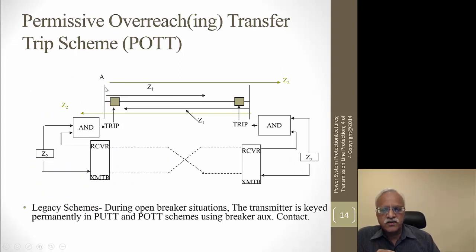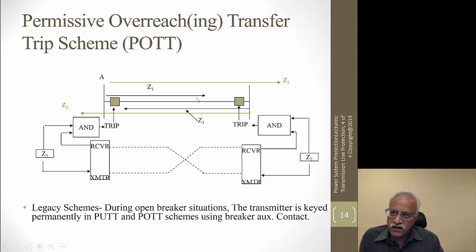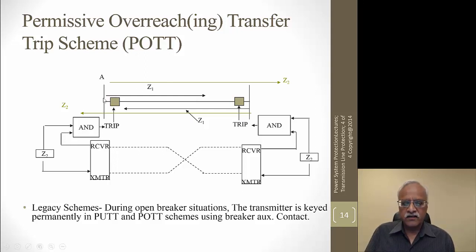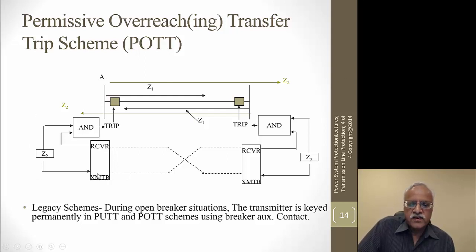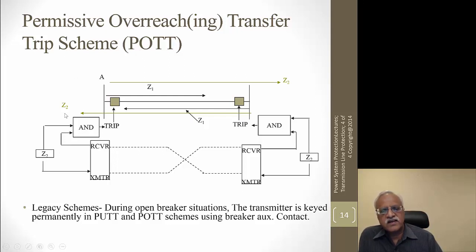Another scheme uses an overreaching zone instead of zone 1 to key the transmitter. Instead of keying with zone 1, zone 2 is used to key the transmitter. Zone 1 can still be used to trip directly without depending on the pilot communication. If there is a fault in 85% to 100% of the line section, zone 2 picks up and keys the transmitter. If a signal is received from the remote end, it trips without time delay. The only difference between this and permissive underreach is that the overreaching element — zone 2 — keys the transmitter instead of zone 1.